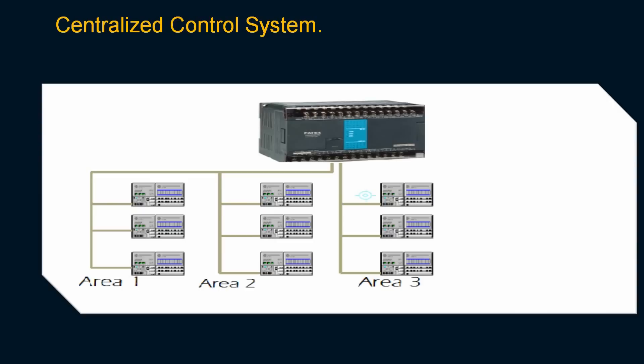First, we will talk about what is a centralized control system. In every plant, there are different units and different processes going on. Every unit or area has its own processes. For example, if you have three areas in one plant — area 1, area 2, and area 3 — and you put one centralized PLC there to control all three areas, what will happen if that controller fails? All areas connected to it are going to be stopped, all the processes are going to be stopped, and the whole plant is going to be shut down.